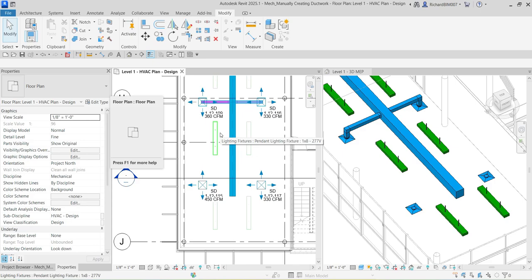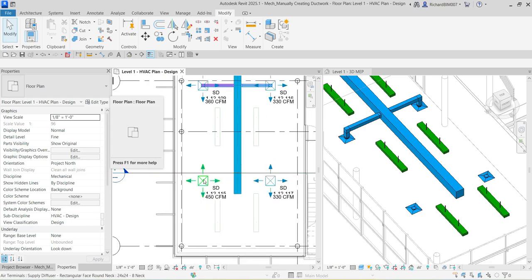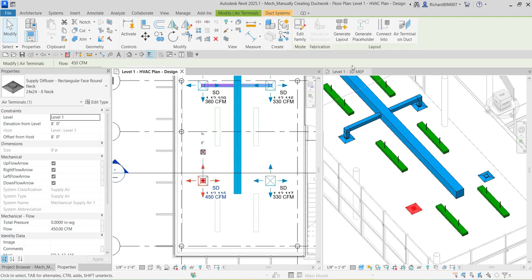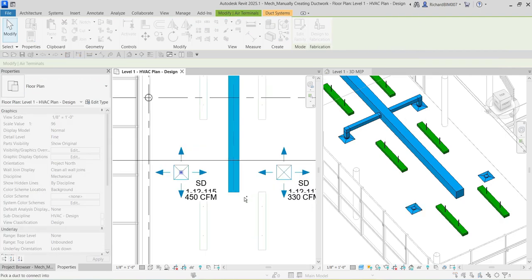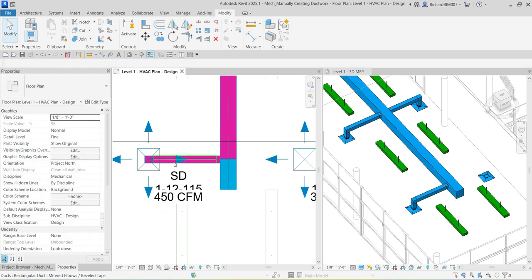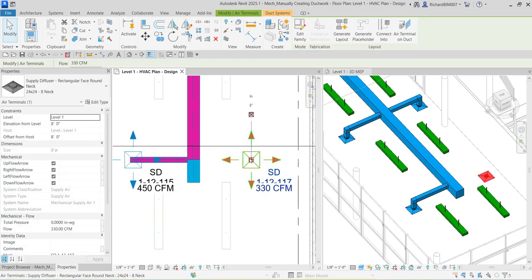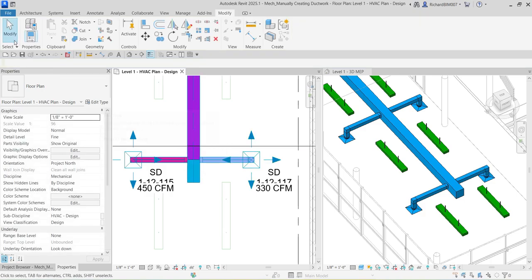We will cover piping in the next video. To use 'Connect Into,' select the air terminal. In the Layout panel, you'll see the 'Connect Into' tool — it creates a physical connection between a selected component and a duct or pipe. Click 'Connect Into,' then select the duct, and it's now connected. Apply this to the other diffusers as well: click 'Connect Into,' click the duct, and then select Modify.